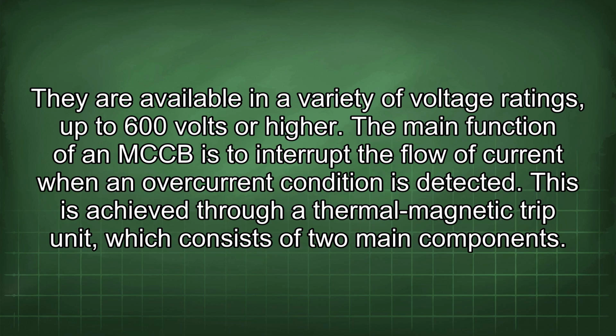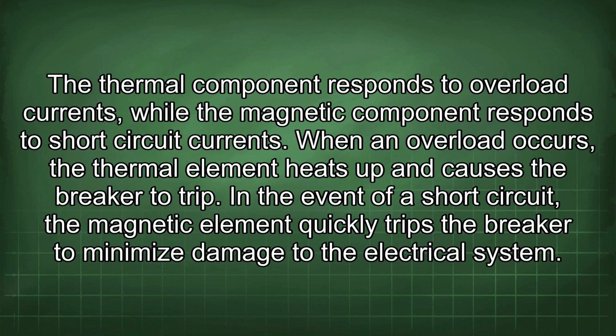The main function of an MCCB is to interrupt the flow of current when an overcurrent condition is detected. This is achieved through a thermal magnetic trip unit, which consists of two main components. The thermal component responds to overload currents, while the magnetic component responds to short circuit currents. When an overload occurs, the thermal element heats up and causes the breaker to trip.